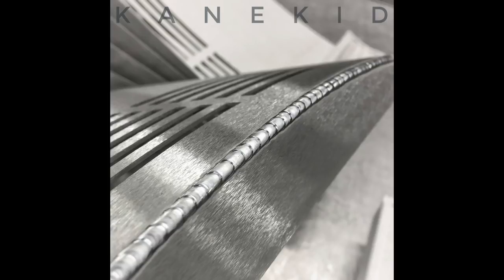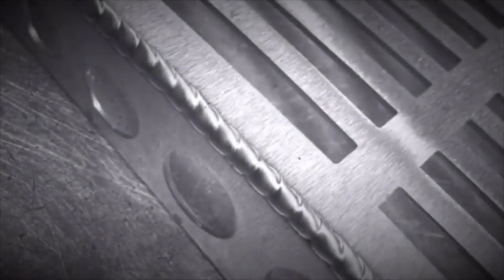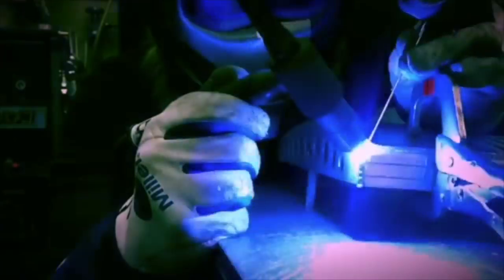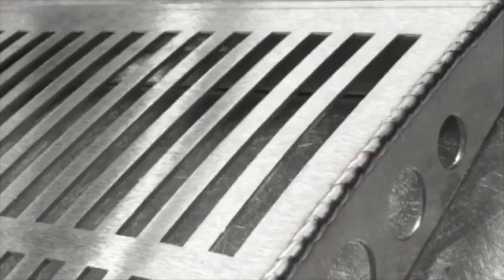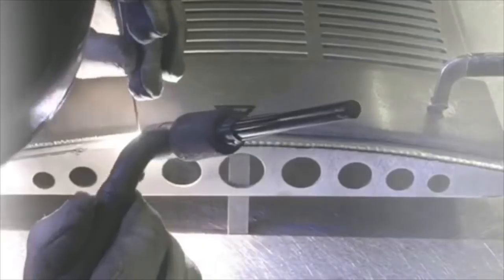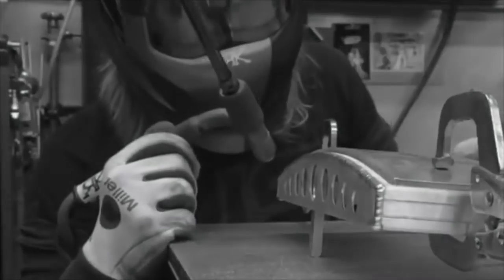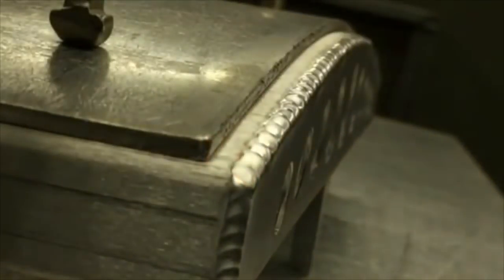That's exactly what it is. I do both a negative vacuum test and a positive pressure test, checking those parts, because you'll have different types of leaks at different pressures. But typically it's a vacuum test where we put a negative pressure on the inside of the part and then spray it with helium wherever the leak is. It'll suck through the part into the testing machine, and it'll sense the helium and the leak rate.